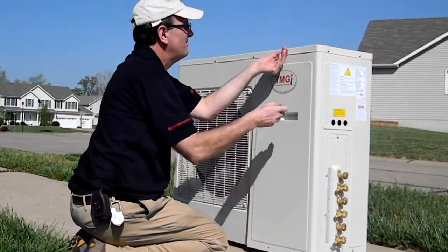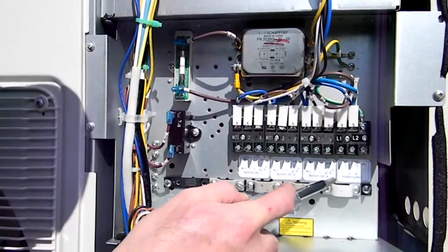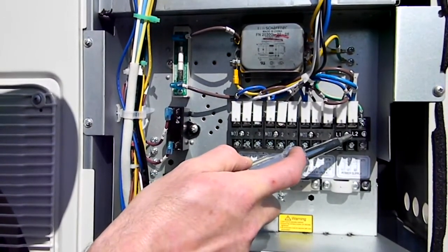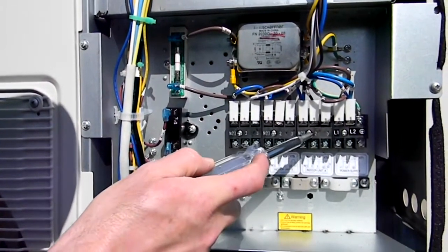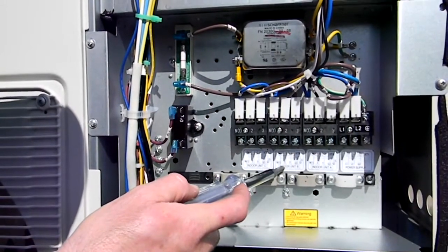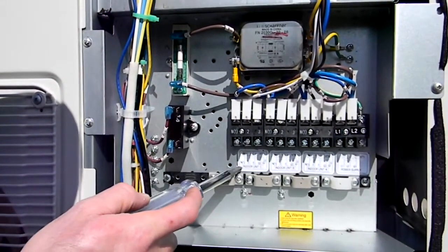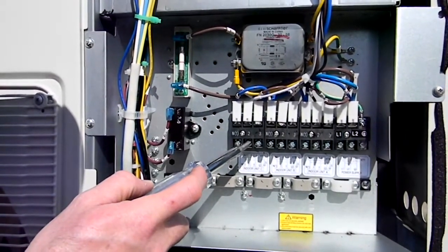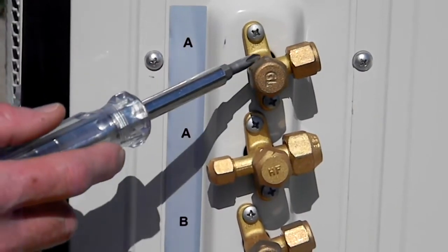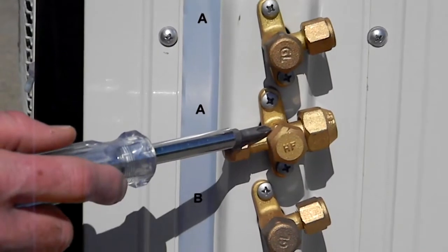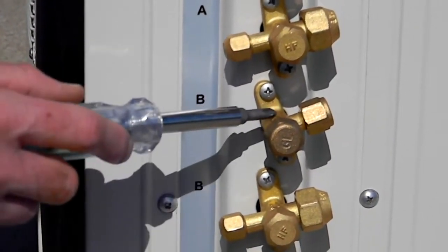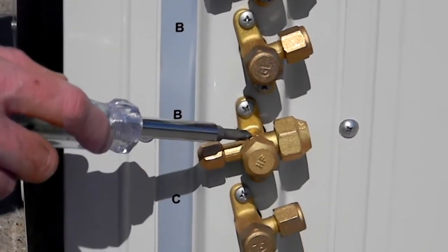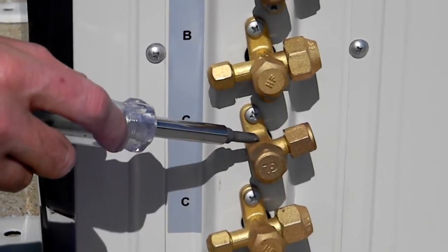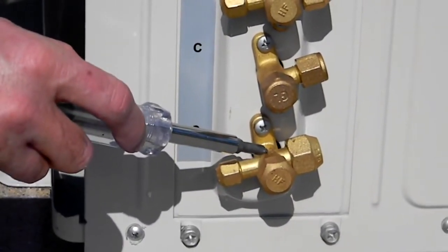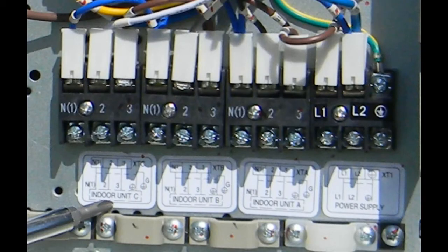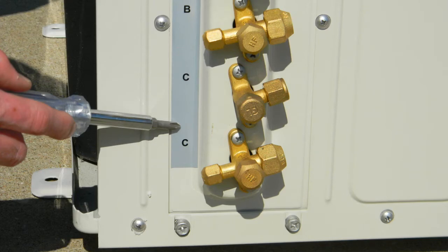Open the electrical panel and note the position of the terminal blocks. Incoming power will go to the far right block, then A, B, C terminals for indoor units A, B, and C respectively. The piping connections are also marked A, B, and C for indoor units A, B, and C respectively. Both the terminal blocks and piping connections are marked to match the zones. The importance of this will be explained in detail later in this video.